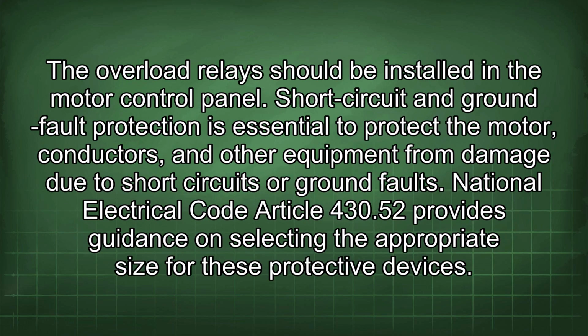The overload relay should be installed in the motor control panel. Short circuit and ground fault protection is essential to protect the motor, conductors, and other equipment from damage due to short circuits or ground faults. National Electrical Code Article 430.52 provides guidance on selecting the appropriate size for these protective devices.